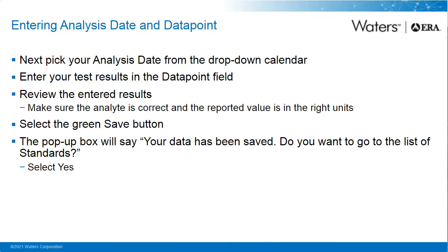Next, pick your analysis date from the calendar. And finally, enter your test results in the data point field. Like we talked about before, this is a really good time to be sure you entered your results for the correct analyte and take note of the units and the concentration ranges. You're actually done. Just select Save and answer Yes to the Return to the List of Standards question.